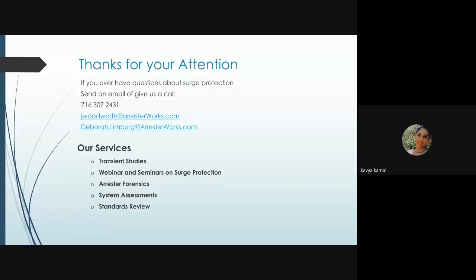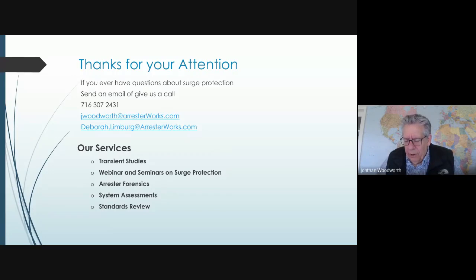Next question. Which type of earthing is good for lightning arrestor? A lightning arrestor doesn't care about earthing. It's almost not relevant. If it's in a bad earth or a good earth, it still works the same. And that seems quite counterintuitive, but arresters usually protect just as well whether there's a bad earthing or a good earthing.